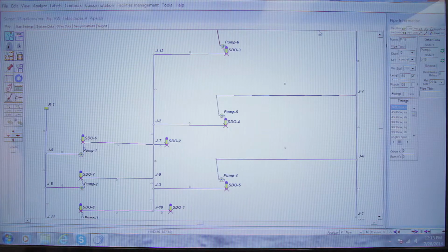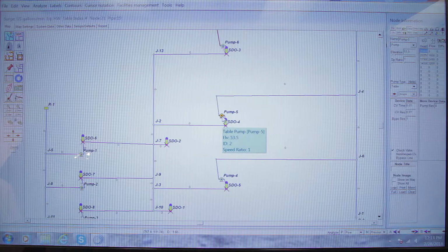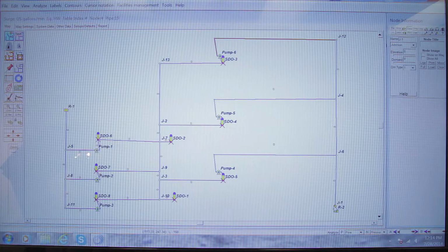So I call this Frack Earth. And it's dealing with high pressure injection pumps. So take a look at this particular pump. We're dealing with 17,500 feet of head in an injection pump. And we look at the cause and effect of a pump trip here. So we can run the model first and foremost. Let me zoom in so you can see, to this point right here.